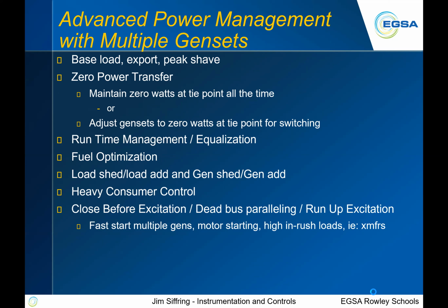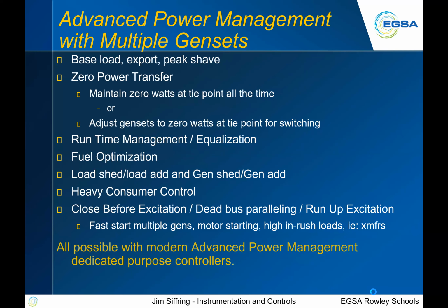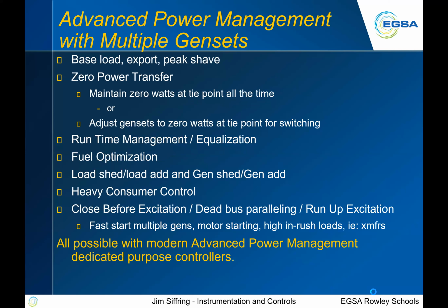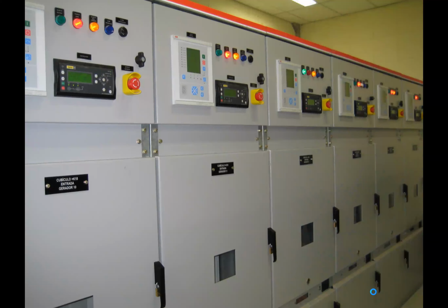Load shedding, load add, generator adds, if you have a lot of consumer control. Then close before excitation, dead bus paralleling, run up excitation for multiple genset starting, and motor starting of high inrush loads, like transformers, which have high inrushes. So all that stuff is possible with the advanced power management dedicated purpose controllers these days. Here is just a photo of a similar system.